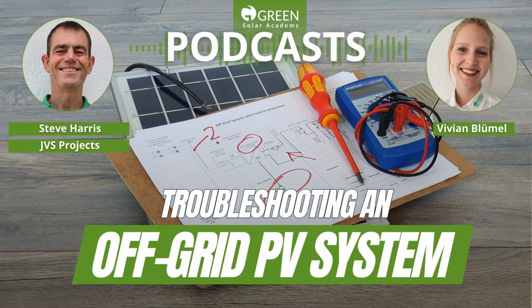And a lot of the inverters, you can set it up to interrogate the fault mode. So it'll record a certain number of faults on its own PC. So you can come along, plug in a computer and download the fault system. But you've got to have set that setting and most people don't set it. So you come along and they say, my inverter's not going. You change it and then come back. And what we have found is with a lot of electronic-based inverters, they're cheaper in the market, they're not transformer-based inverters. When you have repeated faults, it seems to cause a problem with the components and eventually they will fail.